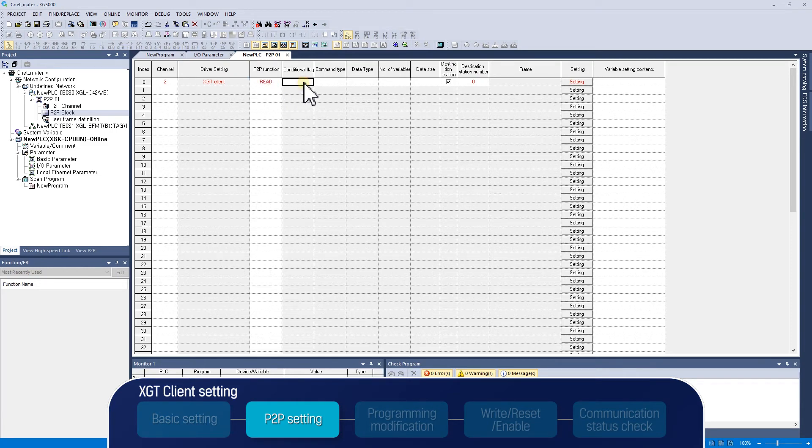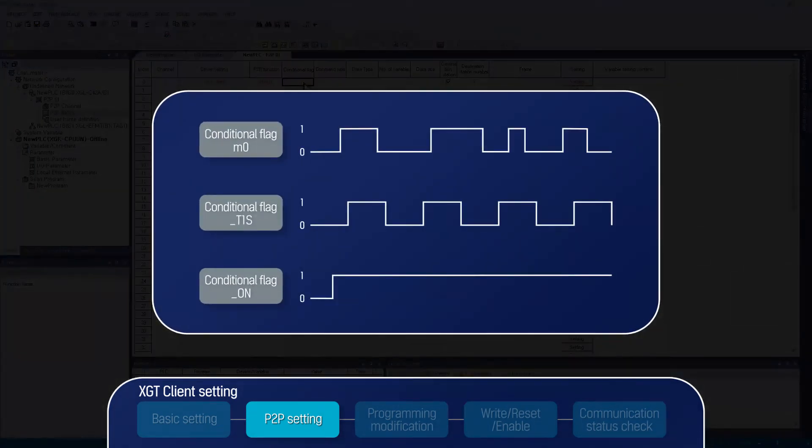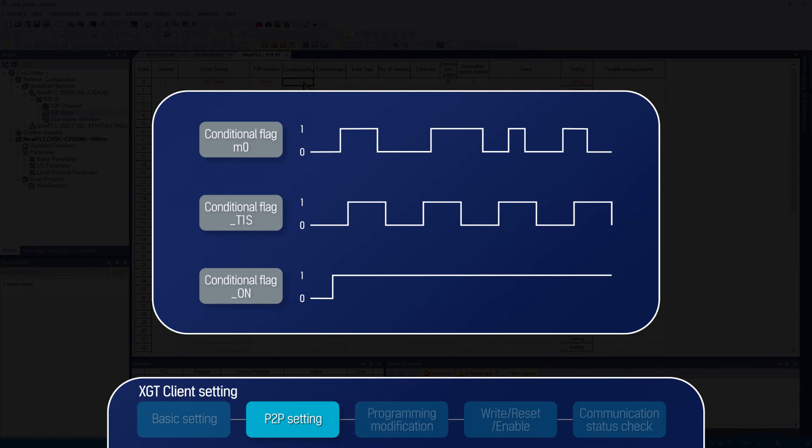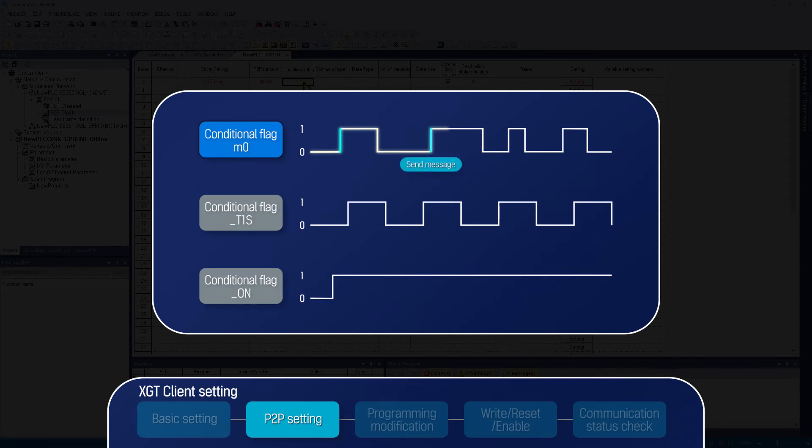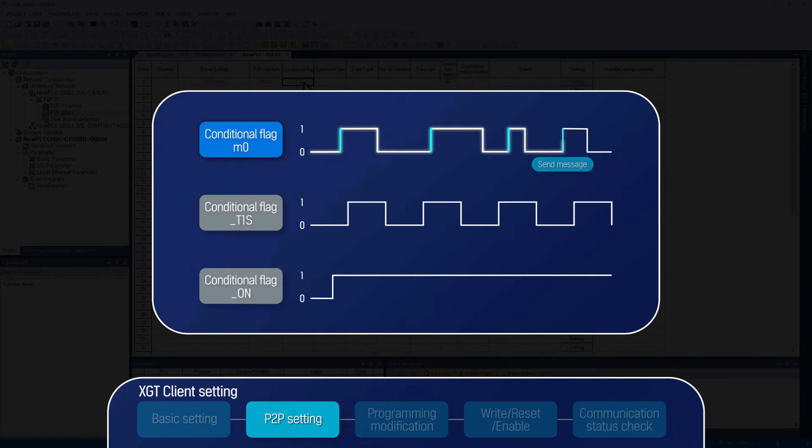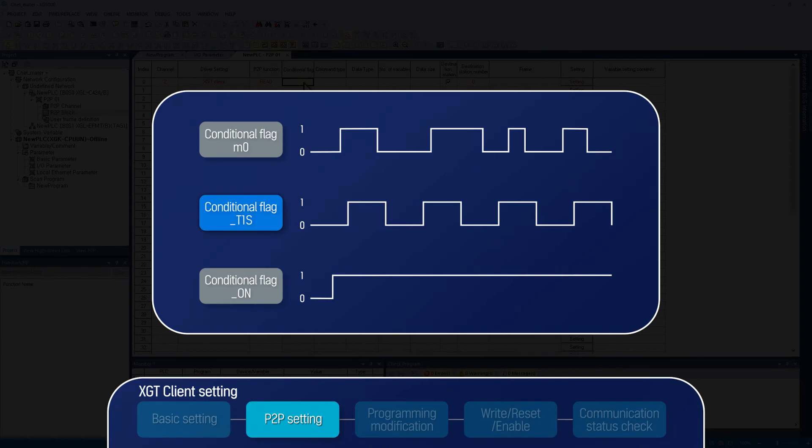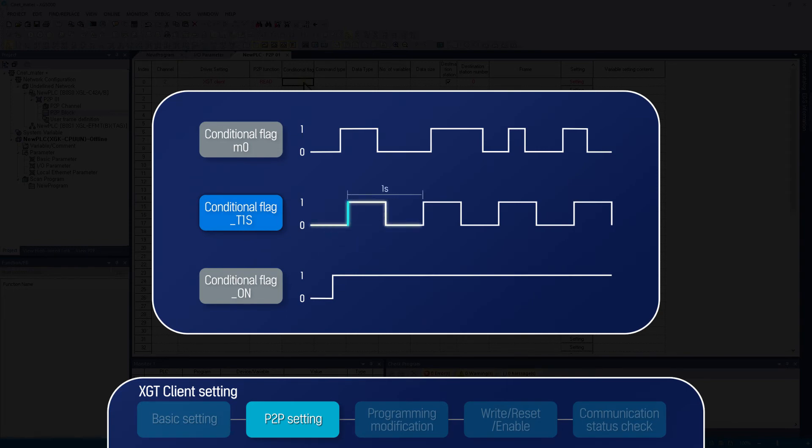We will set the conditional flag. Conditional flag in P2P communication is very important as a communication event occurs when the bit status of the conditional flag turns on. Let's say M0 is the conditional flag, and the communication message is transmitted only when M0 bit changes from 0 to 1. Counter, communication flag, or bit shift commands are generally used as a conditional flag. And you can choose a system flag for a conditional flag as well. For example, if F93 bit one second flag device in XGK is applied as the conditional flag, its communication message will be transmitted at every second.